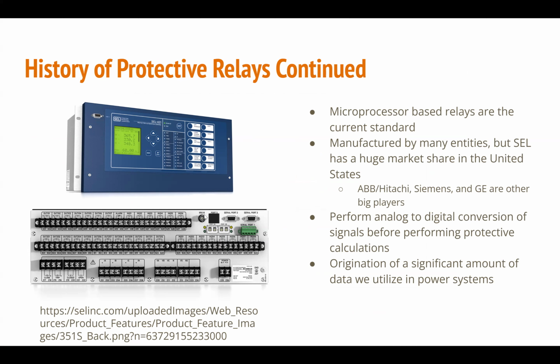So this connection right here that's labeled IRIG-B, that was for time synchronization in the past. But with IRIG-B, you can only get accuracy around 1 millisecond, and we need much higher accuracy than that. Theoretically, we can play with some things to get higher accuracy, but instead we use PTP. So again, that's something we can eliminate with a digital substation. We can use PTP, which is sending time signals over an Ethernet network. And so then we can use these same connections that we're now using for all of our replacements of our hardwired inputs.